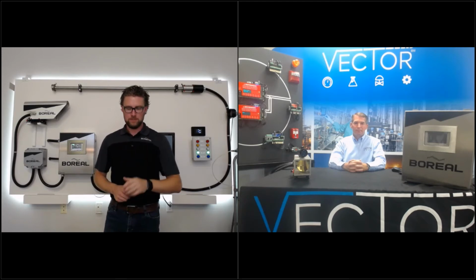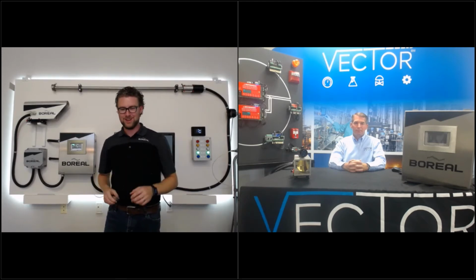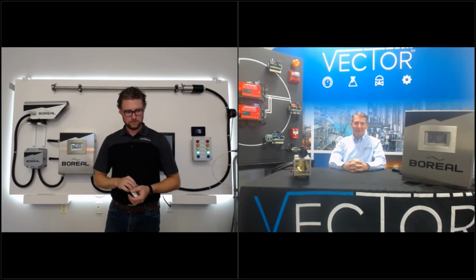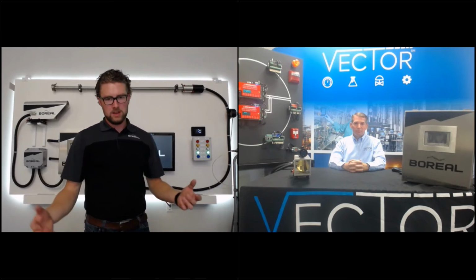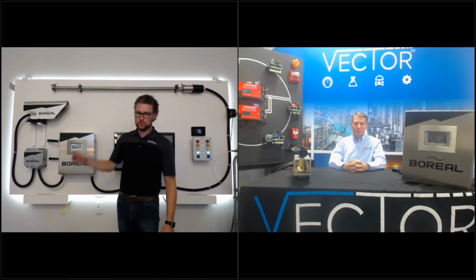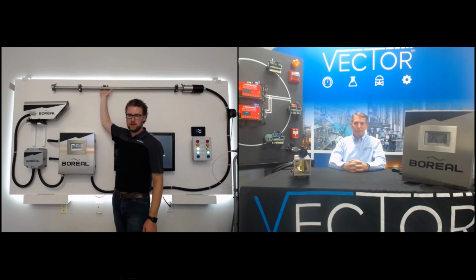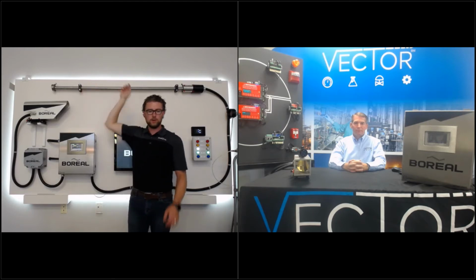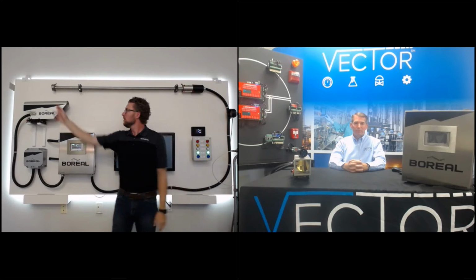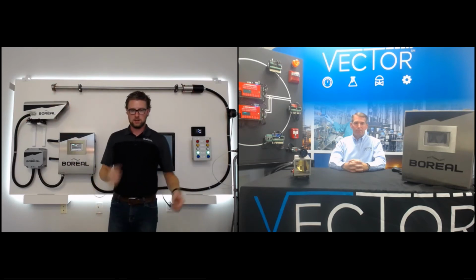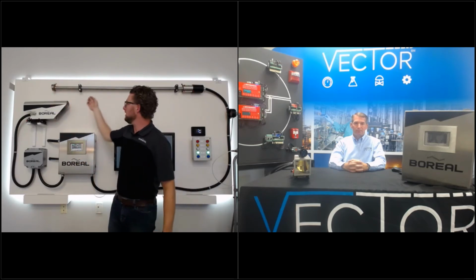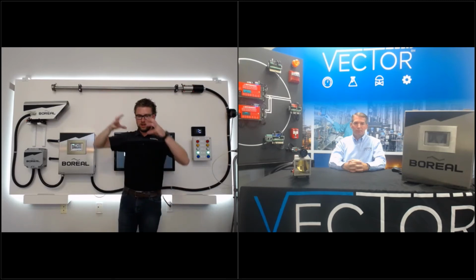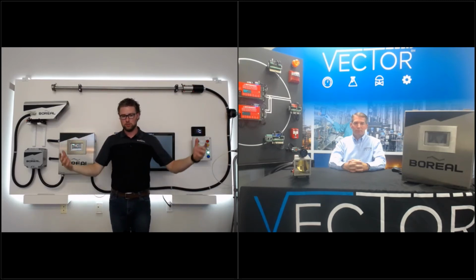As we close up on the last minute of my scheduled talking time here, another important component to talk about is some of the additional measurement heads that we have available. Above me here, we have an extractive measurement cell. This enables you to tube in process conditions and flow through these arrangements. So you have a process in, process out arrangement, and you can make direct non-contact measurements. These are available with fully customizable tube length to justify your detectable range.